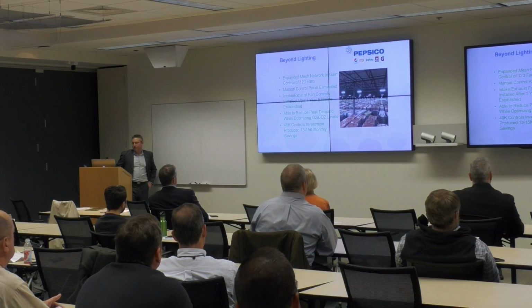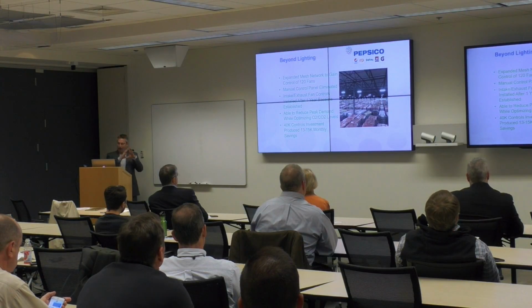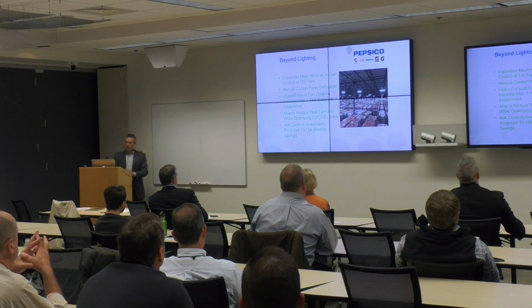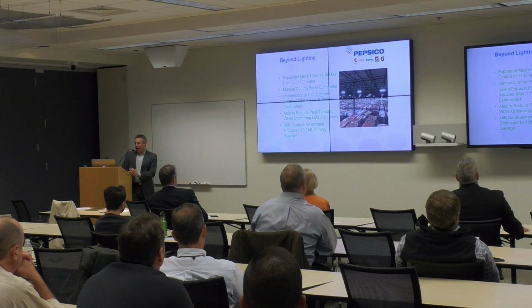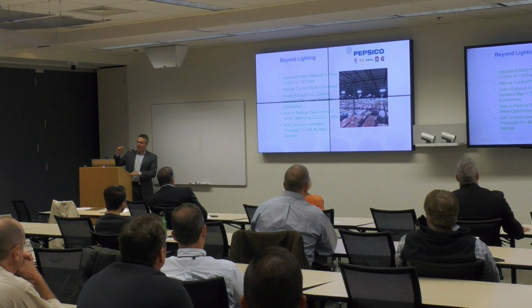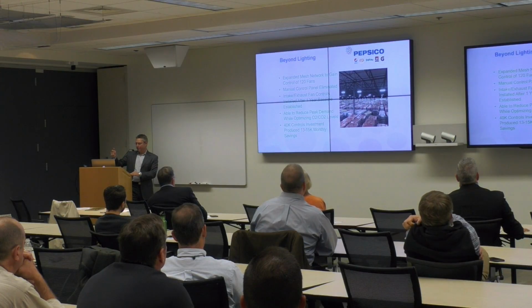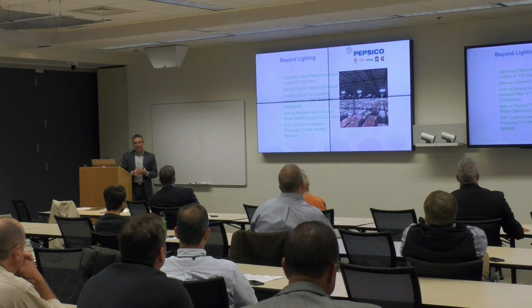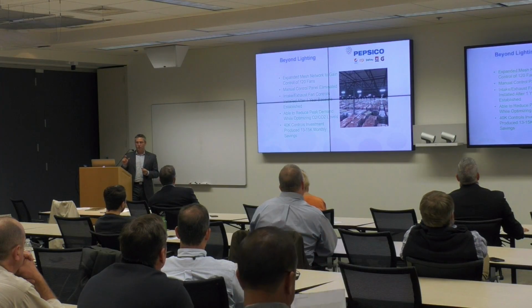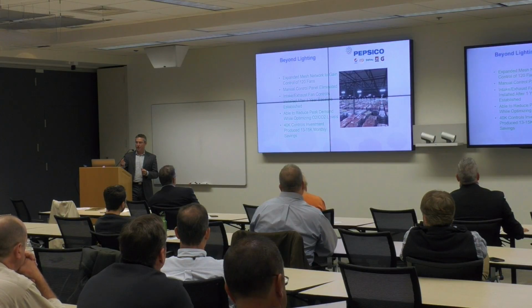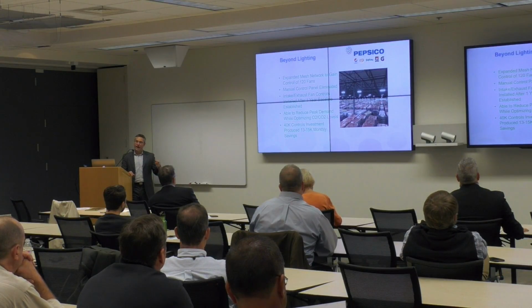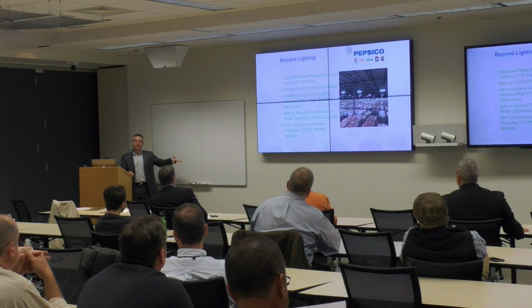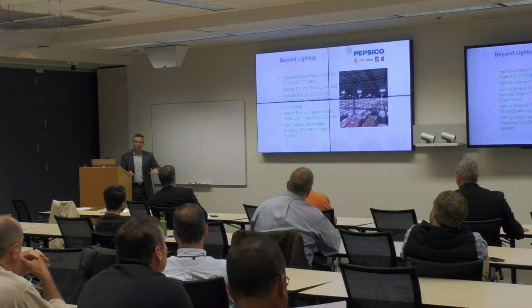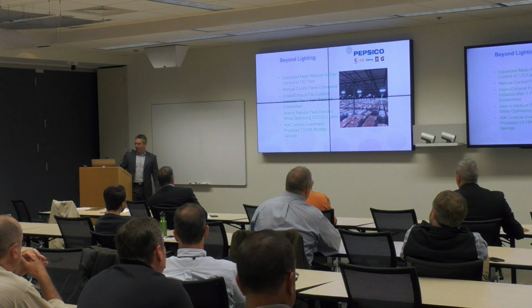Kathy, back to your question, what we also did was take that network of sensors and integrate it with the fans. Because you've already got the whole network in place, the add-on benefit gives an incredibly fast payback. The add-on cost of the controls for the fans was $40,000, and the savings for the fan controls was $13,000 to $15,000 a month. So you get payback in like 3 months on that additional piece. It really shows how piggybacking multiple applications onto one network and one set of hardware and controls gives you tremendous additional value.